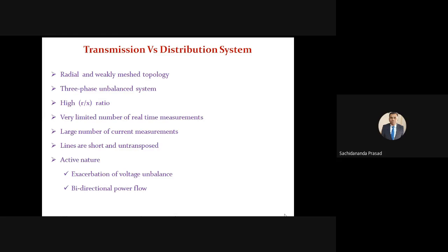Resistance of a line is more than the reactance, which is not the case in a transmission system. So the methods used for transmission system state estimation cannot directly be used for the distribution system. This is the problem we are facing. The load flow technique used for the transmission system cannot be directly used for the distribution system because of these issues, because of the high R/X ratio. Your algorithm won't converge—there is an issue related to convergence of the algorithm.